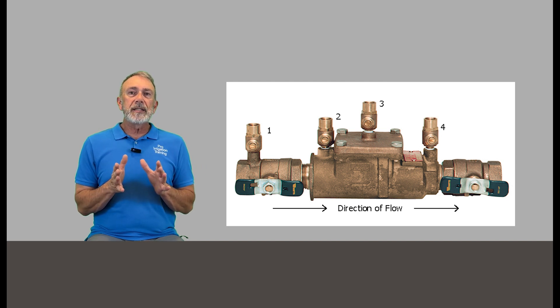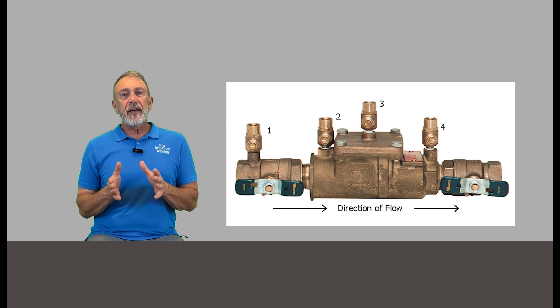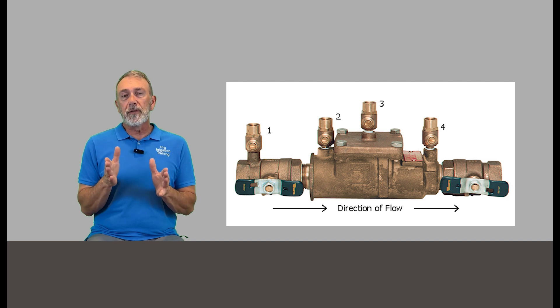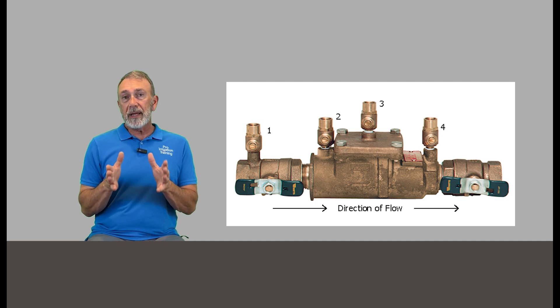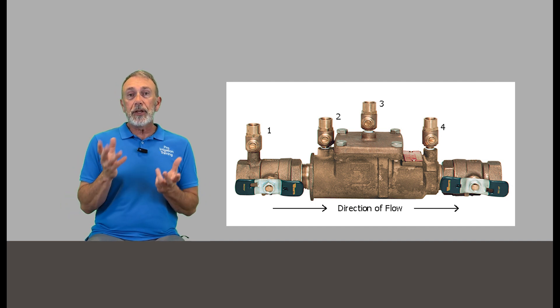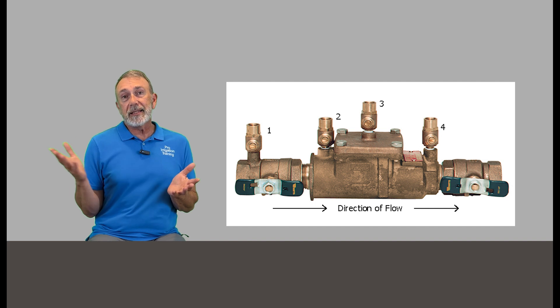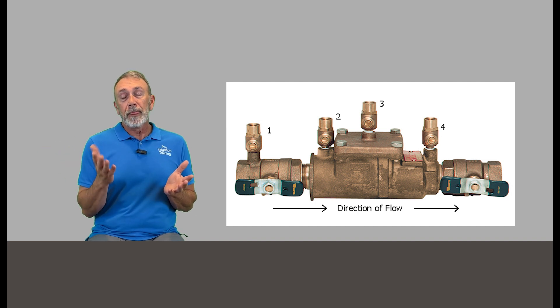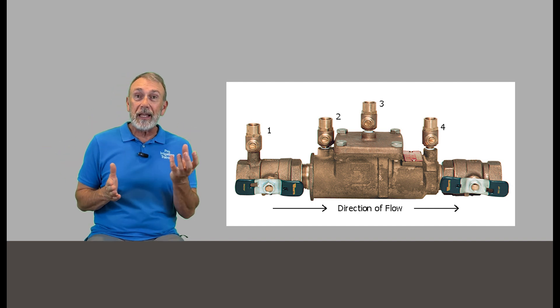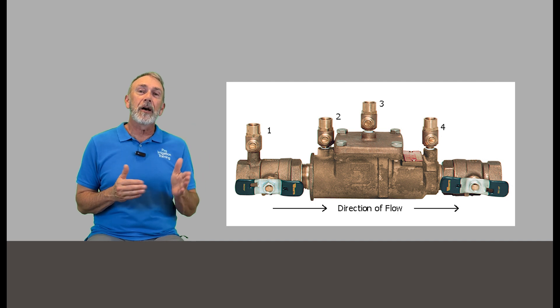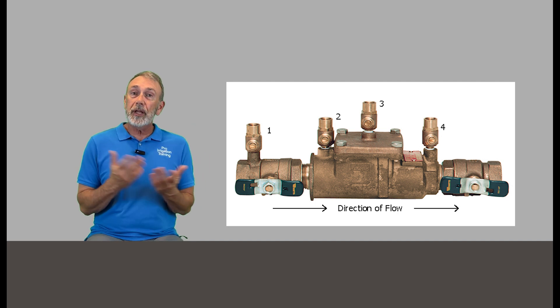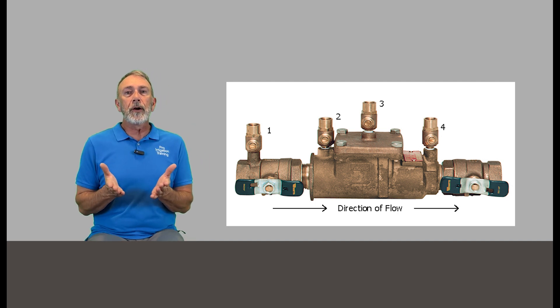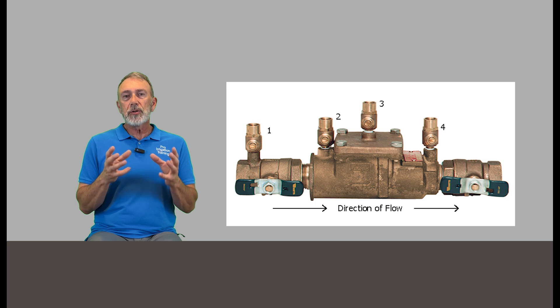On test cock number one, we're going to check the pressure and then we're going to move the gauge to test cock number four, the last one, the furthest away from the meter, put our gauge on there and then check the drop across the device. Most of these devices say that you can have up to a seven or 10% drop across the device and it not be defective. But if you see a huge one, say you've got 80 PSI as your input pressure on test cock one and then 30 on your exit pressure on test cock four, it's a problem with the backflow preventer rebuild or replace.